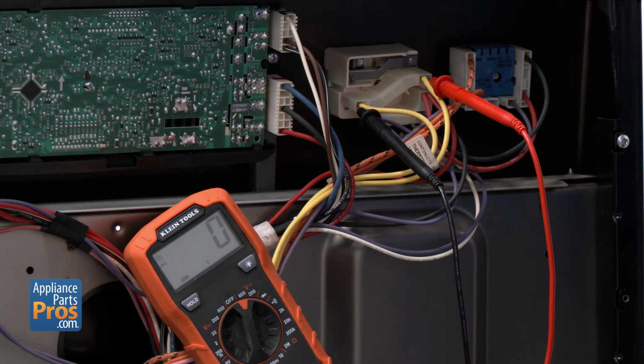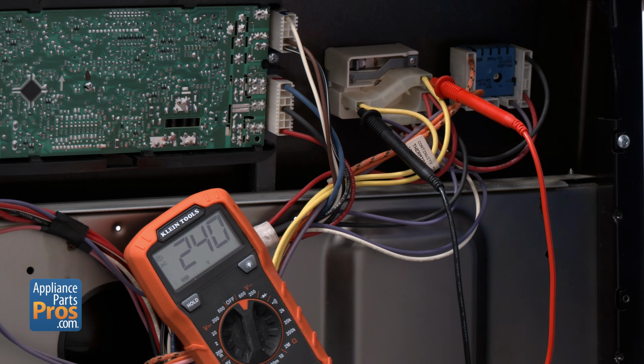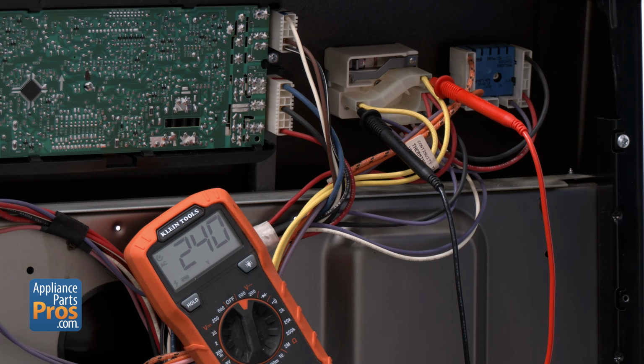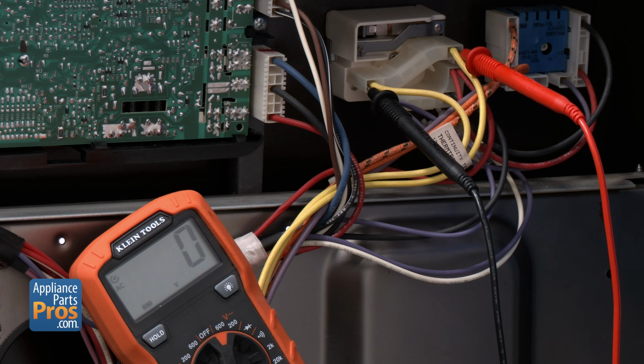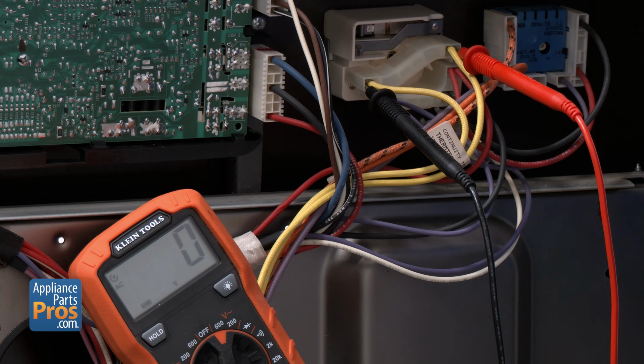Now rotate the element switch to the high setting. Place one probe on the yellow wire at terminal H2 and the other probe on the yellow wire at terminal H1. You should see 240 volts AC. Keep the probes in place to get a voltage reading when the element shuts off. If the voltage stops when the element turns off too soon, the infinite switch has failed.